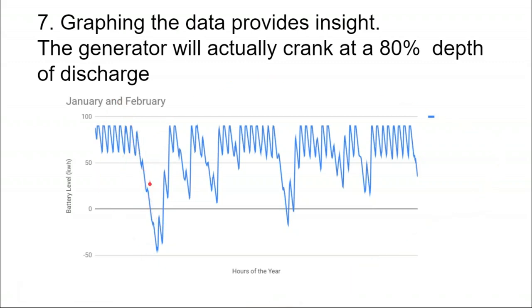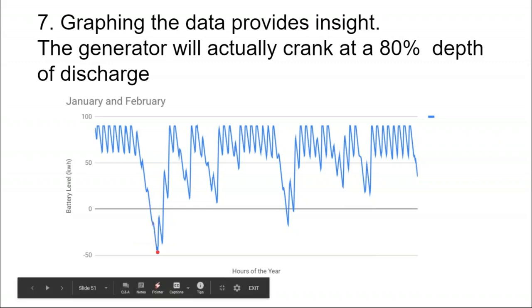In this model, which does not have the generator built in, I go through a cloudy day, a cloudy day, and a cloudy day. We can see that it doesn't really matter how much solar would have been on the roof during this cycle, because on this particular day we're getting nothing out of our solar array. It didn't matter how large a solar array we had on the roof. By the time we get through day one, day two, by the time we get 3 days into our cloudy weather cycle, it's time to crank the generator.